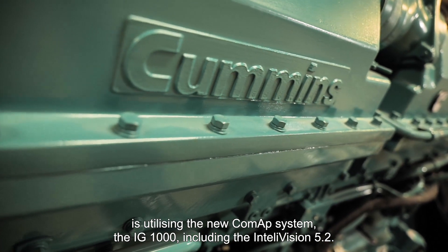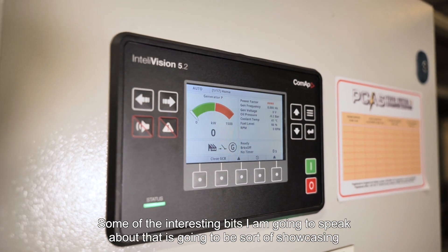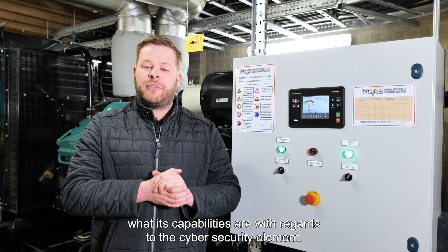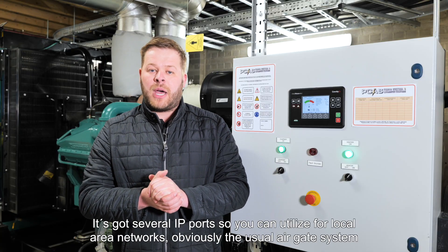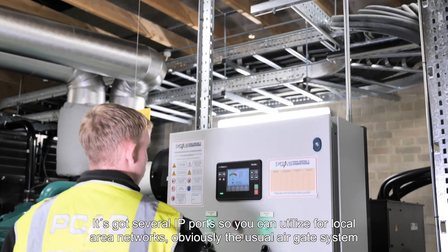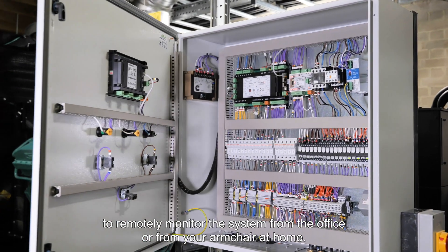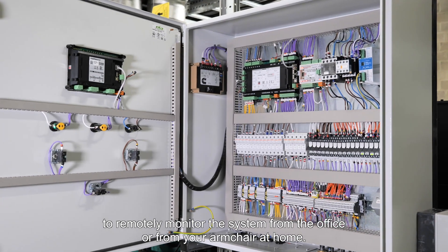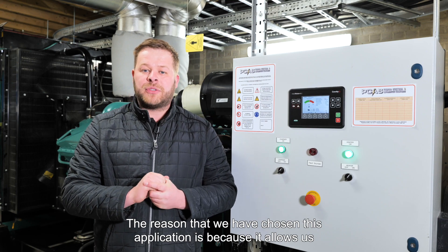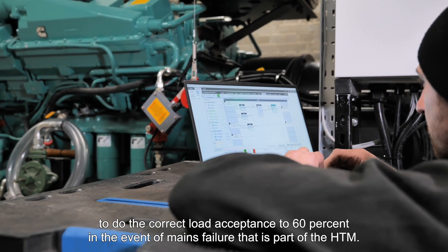The interesting part of this project I want to bring to your attention is utilising the new COMAP system, the IG1000, including the InteliVision 5.2. I'm going to be showcasing its capabilities with regards to the cyber security element. It's got several IP ports that you can utilise for local area networks, the usual air gate system, and going out to your own data centre to remotely monitor the system, either from the office or from your armchair at home. The reason we chose this application is because it allows us to do the correct load acceptance to 60% in the event of a mains failure, which is part of the HTM.